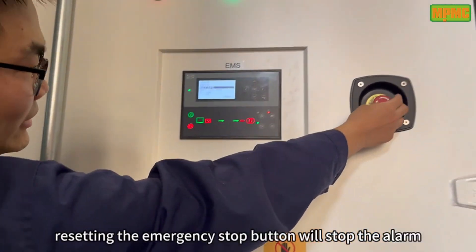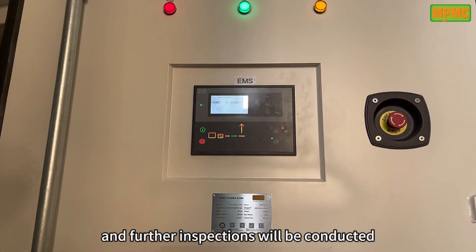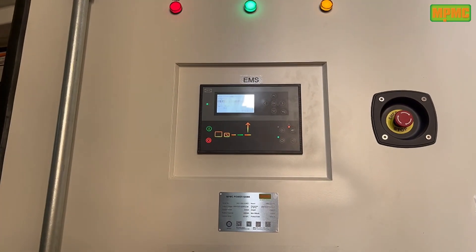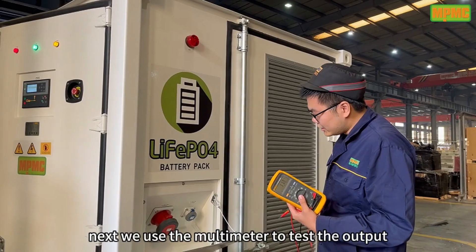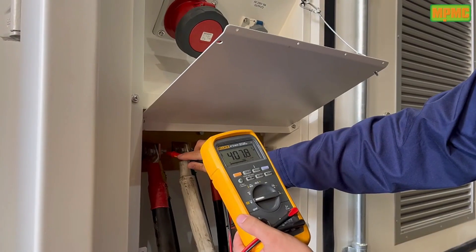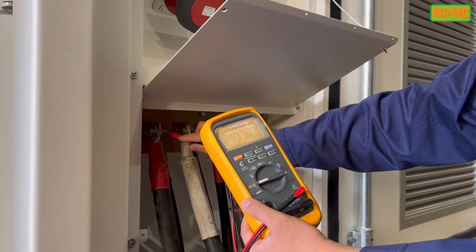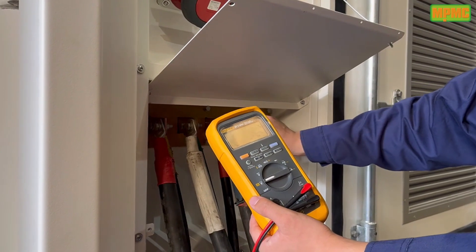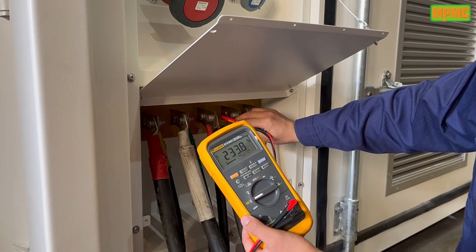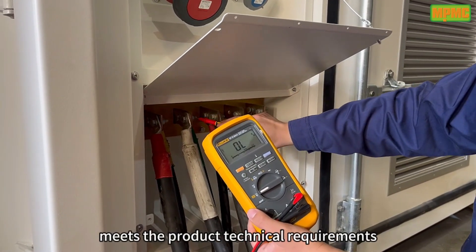For resetting, the emergency stop button will stop the alarm, and further inspections will be conducted to resolve the product issues. Next, we use the multimeter to test the output voltage of the BSS. The line voltage is 407V. The phase voltage is 233V, and the voltage fluctuation range meets the product technical requirements.